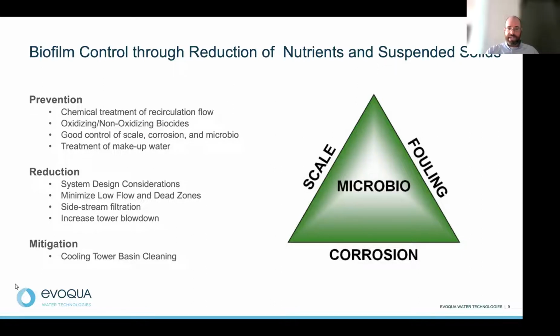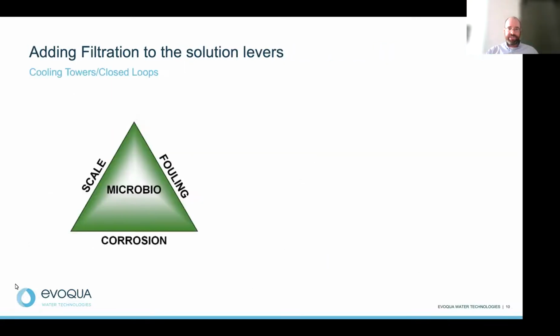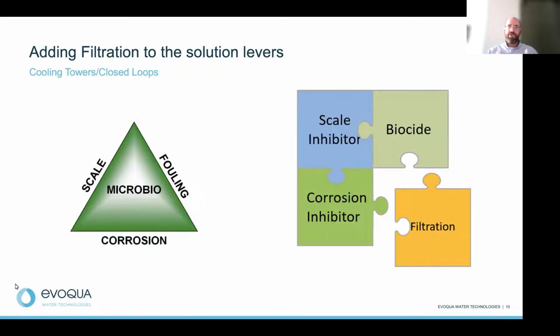So if we look at these systems, and there's our cooling water triangle again, we talked earlier about one of the things a lot of you most likely do is you use scale and corrosion inhibitors, as well as oxidizing and hopefully non-oxidizing biocides. Well, I would argue that filtration is the missing puzzle piece to helping you have a system that allows you to not have scale, corrosion, bacteria, and fouling. And so you're putting those chemicals in there and they're doing their job, but they can't do their job if you've got a lot of debris in there.